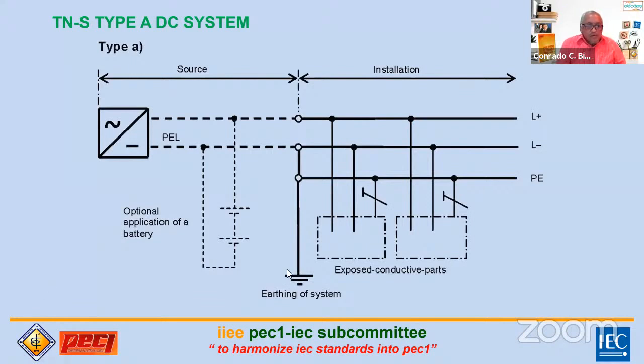Now, the earthing arrangement in the DC system, like in battery systems or UPS, this is how it's done. We have a source here, the positive and negative, L plus and L minus. This battery is optional. Then you have the source and the installation. How it's connected, the negative is grounded. It's like our vehicles, where we see that the negative is grounded to the body. So this is how the installation is done in a DC system.